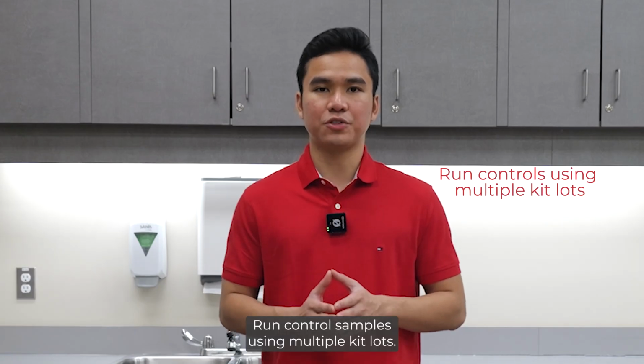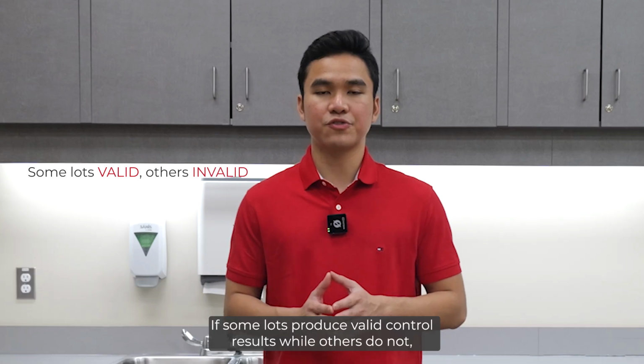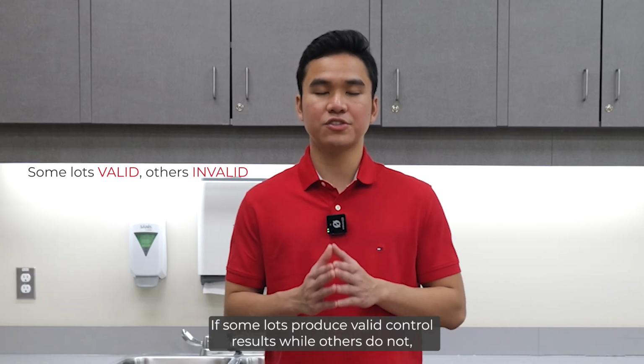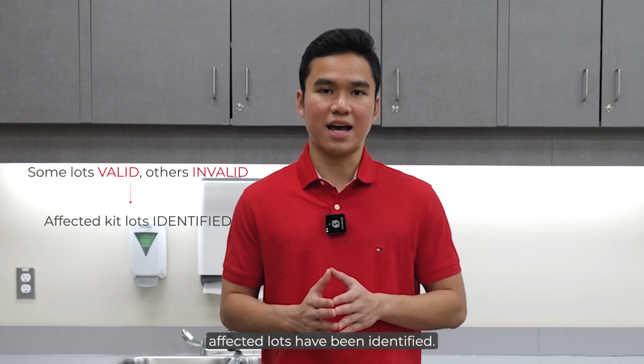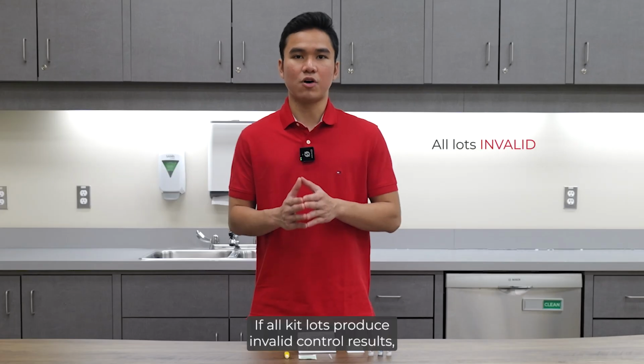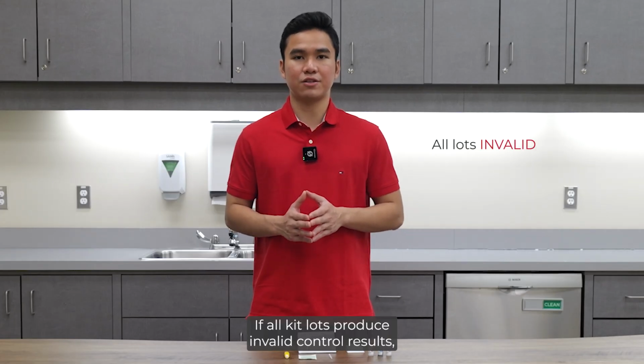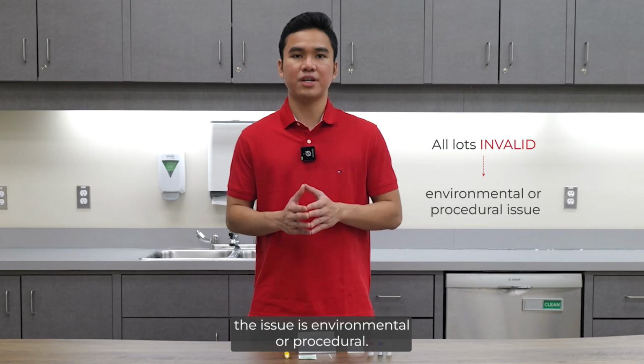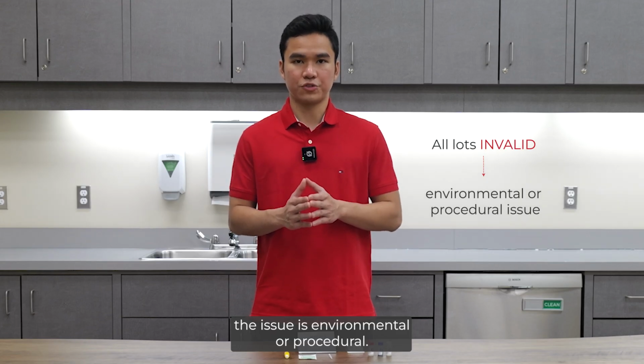Run control samples using multiple kit lots. If some lots produce valid control results while others do not, affected lots have been identified. If all kit lots produce invalid control results, the issue is environmental or procedural.